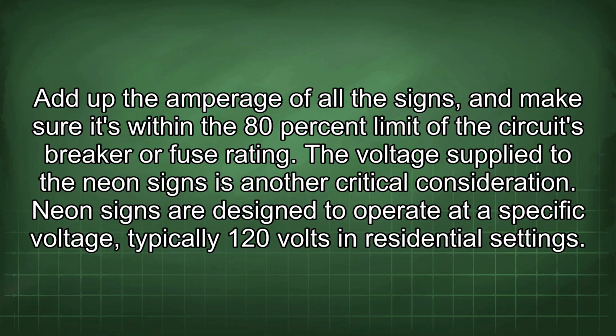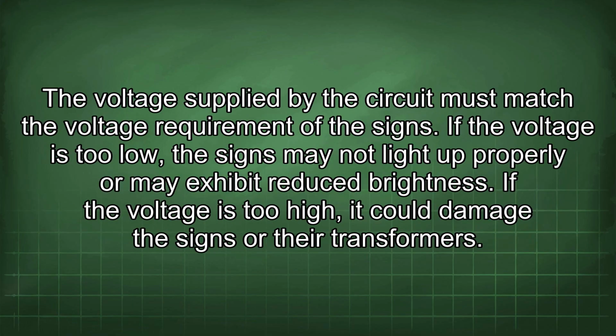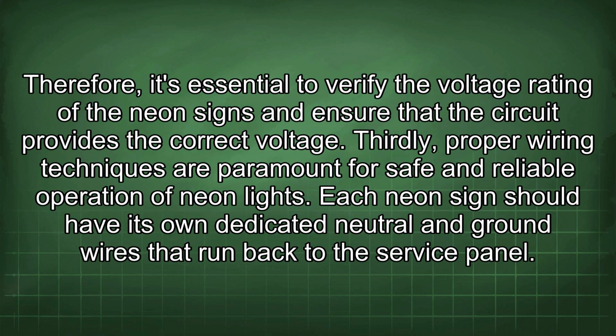The voltage supplied to the neon signs is another critical consideration. Neon signs are designed to operate at a specific voltage, typically 120 volts in residential settings. The voltage supplied by the circuit must match the voltage requirement of the signs. If the voltage is too low, the signs may not light up properly or may exhibit reduced brightness. If the voltage is too high, it could damage the signs or their transformers. Therefore, it's essential to verify the voltage rating of the neon signs and ensure that the circuit provides the correct voltage.